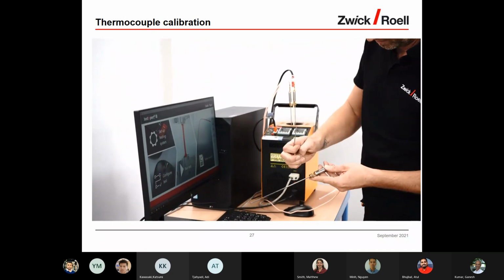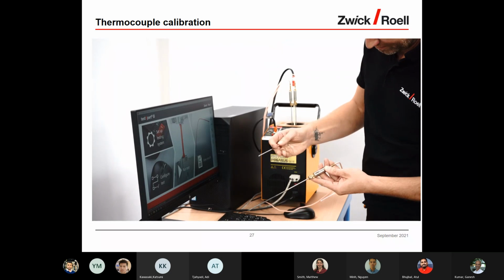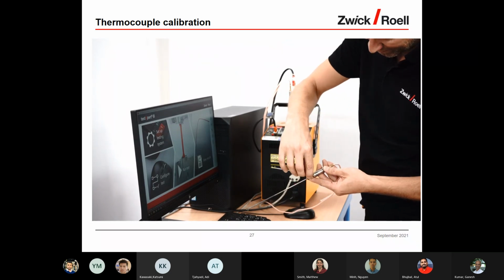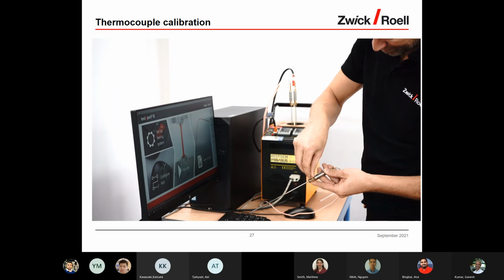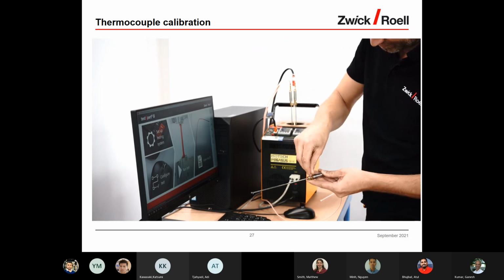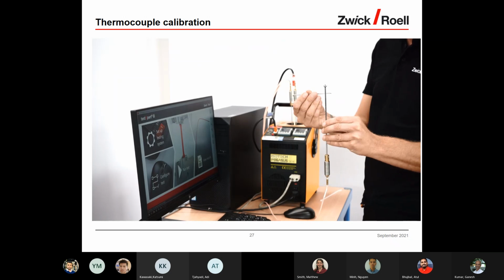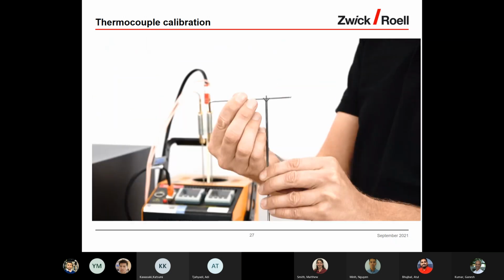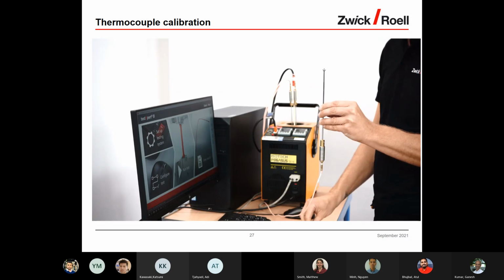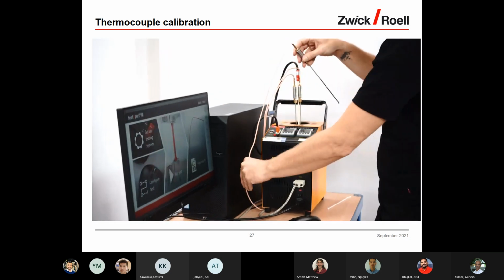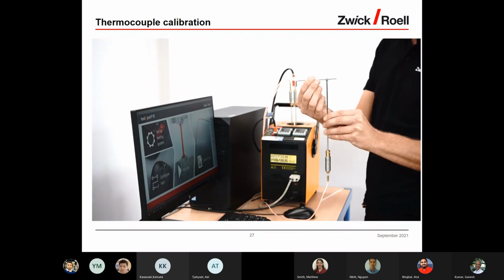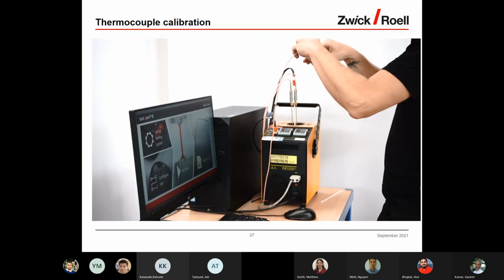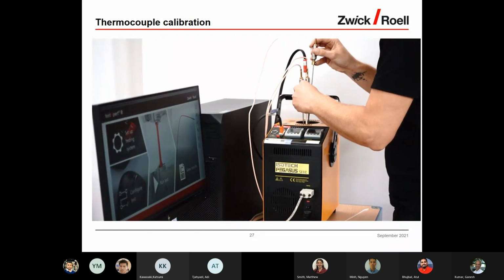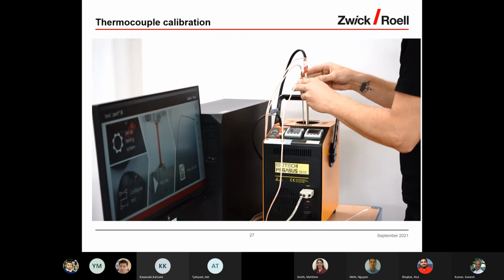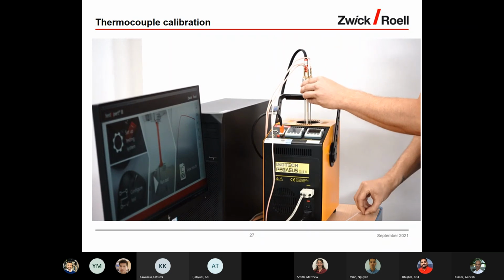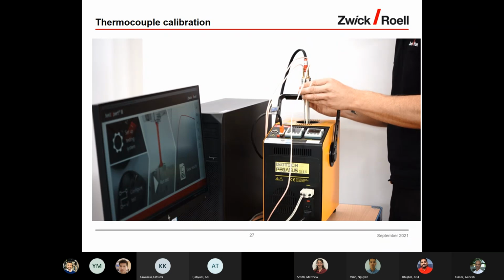Open the screw to slide the Inconel protective cover backwards. Tighten the screw again. Here you can see the thermocouple must be free. Now the thermocouple is plugged to the other thermocouples and the reference element. And now I fix them together.